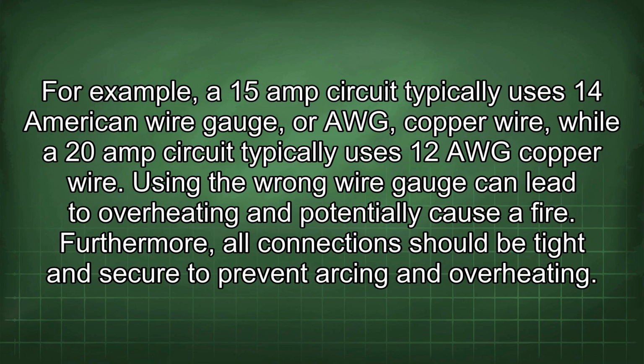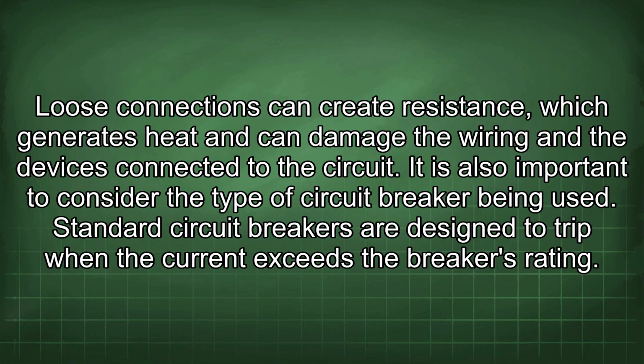For example, a 15 amp circuit typically uses 14 American wire gauge, or AWG, copper wire, while a 20 amp circuit typically uses 12 AWG copper wire. Using the wrong wire gauge can lead to overheating and potentially cause a fire. Furthermore, all connections should be tight and secure to prevent arcing and overheating. Loose connections can create resistance, which generates heat and can damage the wiring and the devices connected to the circuit.